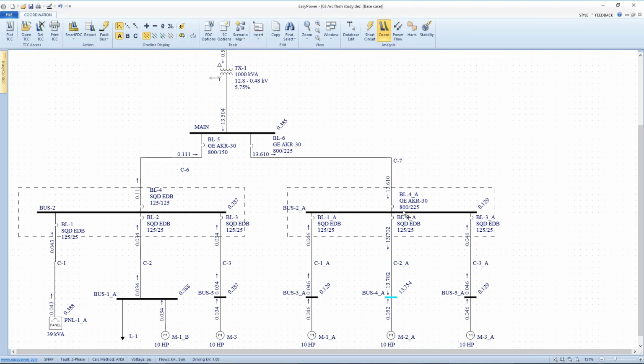But if I look upstream and at these sister branches, I can see the contribution current that each one of these remote buses is making to my isolated fault. The significance of that is all of this extra current could actually be impacting and or interfering with the coordination of my plant.